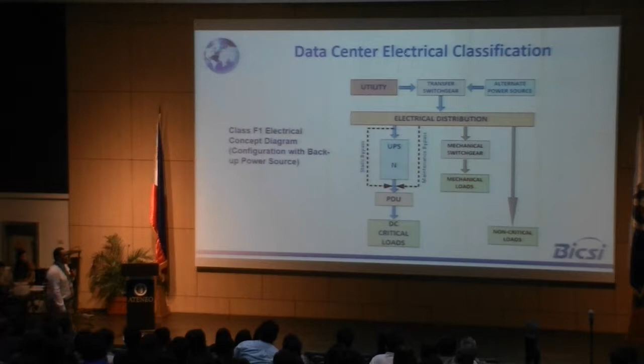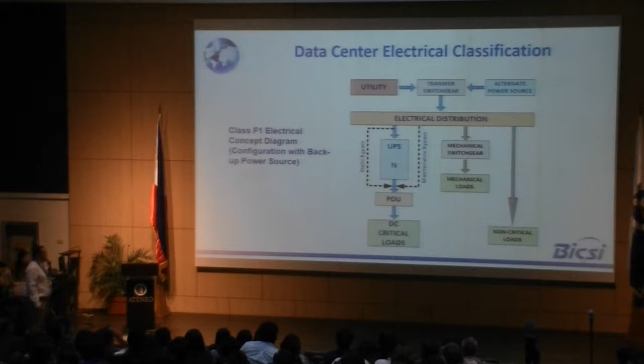Same setup, except your UPS now has static bypass and maintenance bypass. That's just a maintenance bypass, no external bypass yet. Then you have mechanical switchgear, mechanical load, then again your data center, server, or computer room, or communication room requirement is supported by UPS. So that is your DC critical load. This is the F1 electrical concept diagram.